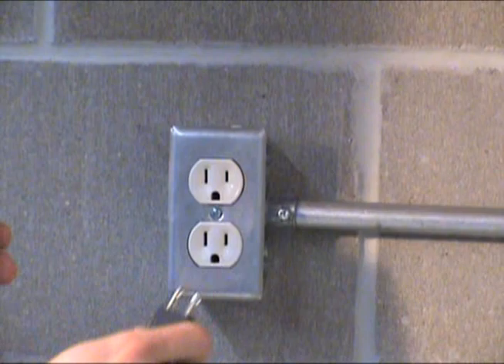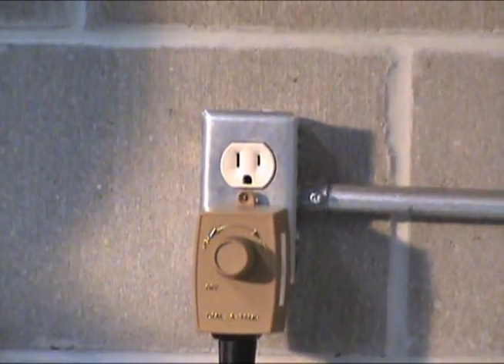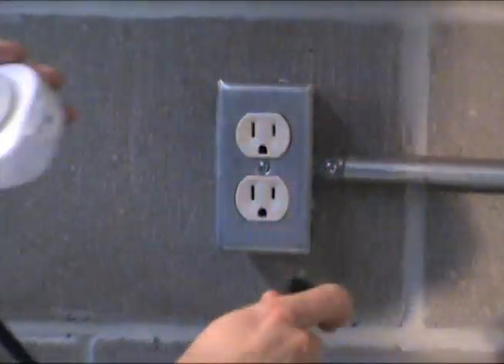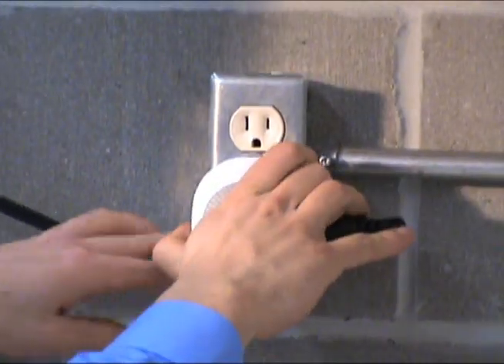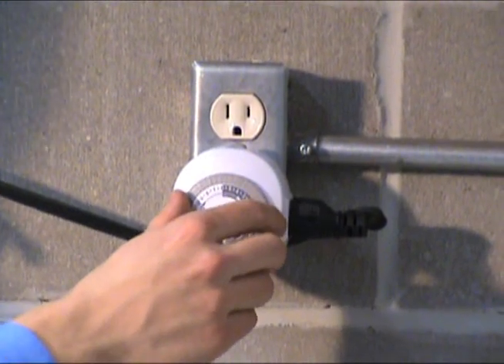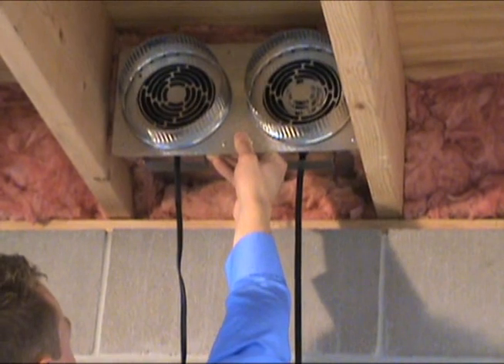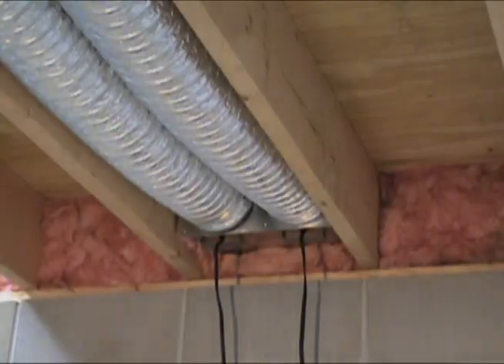Add the optional plug-in speed control if you need less than 90 CFM per fan. Use a plug-in timer to cycle the exchanger when desired, or replace the rear fan guard with the optional duct takeoffs to run 6 inch duct to an adjacent room.